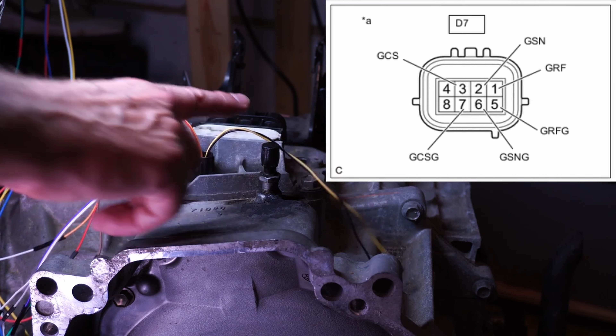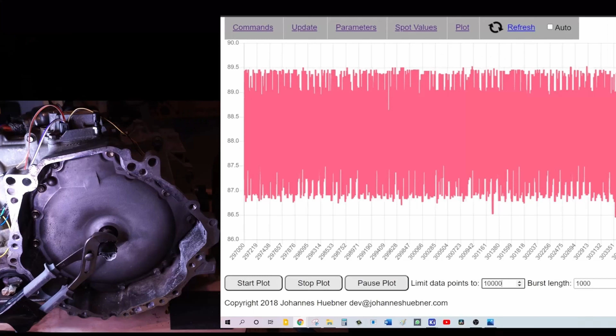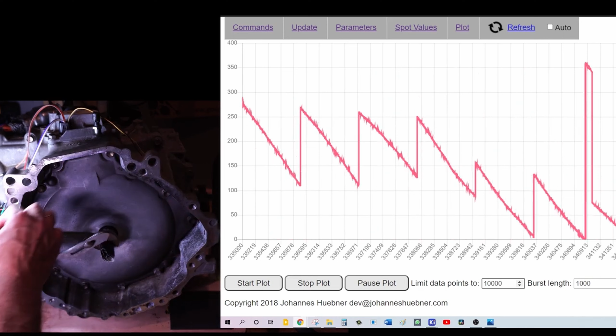I connected the resolver as per diagram, and now it was time to test if it gives us the right reading. Now I'm going to rotate the motor and we're going to see what's happening with the signal. Okay, so we are getting a good reading now, and you can see that the encoder is reading from 0 to 360 degrees.